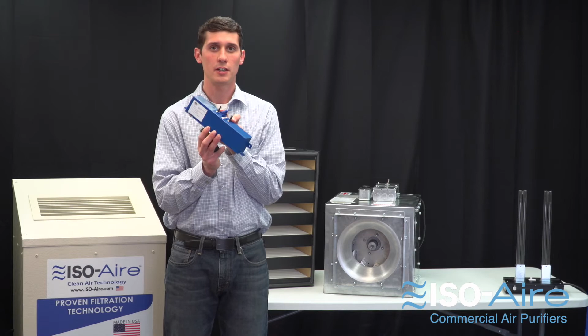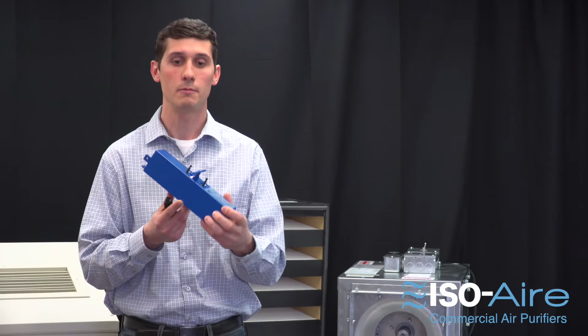Ozone-free bipolar ionization. Again, a lot of talk these days about ionization, ionization, ionization. Seen a lot of people install it. It can work great, but there's some caveats. First off, how does it work? It uses these brushes here. This is a needlepoint bipolar ionization. We like this design of ionization because it's very low maintenance, it cleans itself, there's no tubes to replace. It's a nice set it and forget it kind of design.